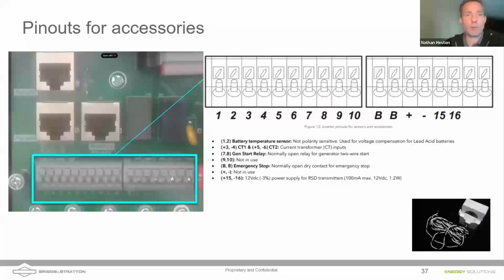So the pin out here for the accessories, there are a number of things to point out, maybe just highlight a couple of them. So if you're wiring in the CTs, you would use pins 3 to 6. If you have an external battery temperature sensor, now our communicating batteries will communicate that information directly to the Sol-Ark, but if you had an external sensor, you can use that through ports 1 and 2.